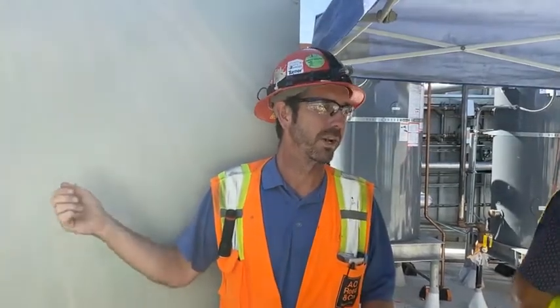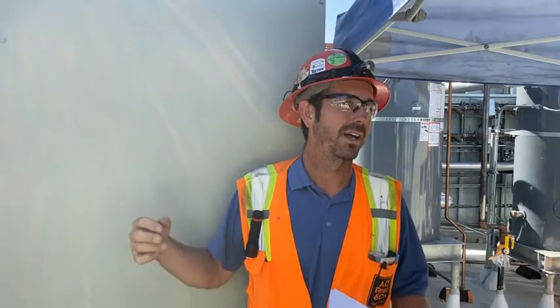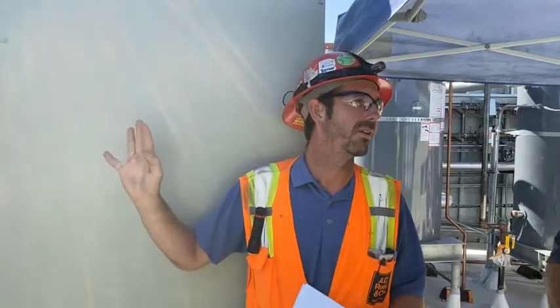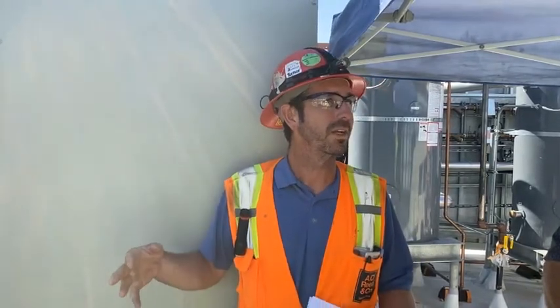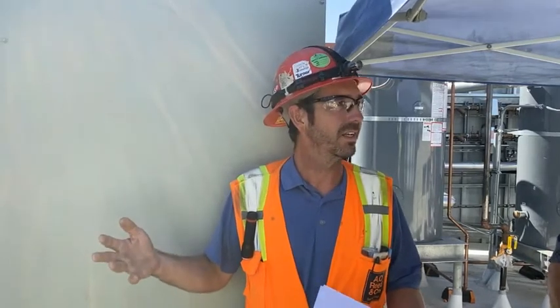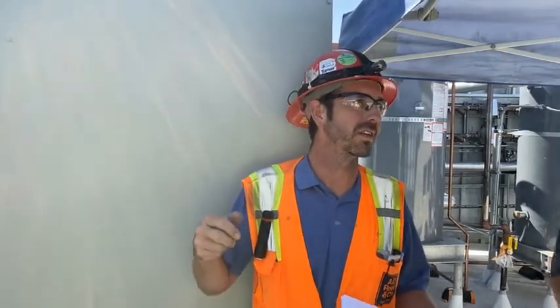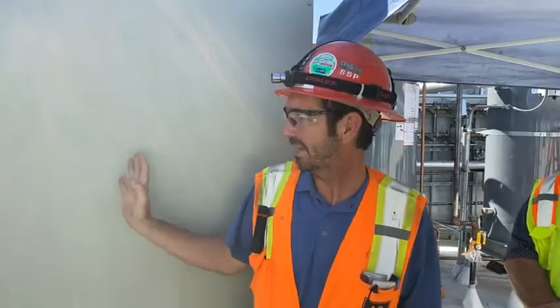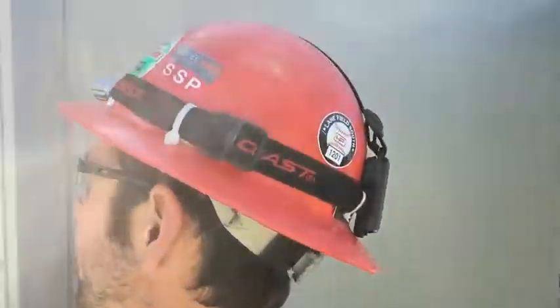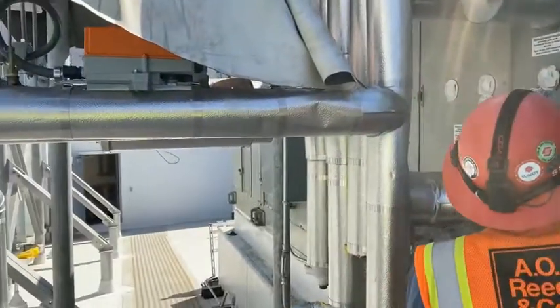They still can get dirty. Okay, they are a filter. So you'll want to clean those. Since that is the first filter, I would definitely inspect it monthly, but clean as needed. You'll be able to see when they start getting dirty, okay? After that set of filters, we go inside the unit, into the filter compartment.